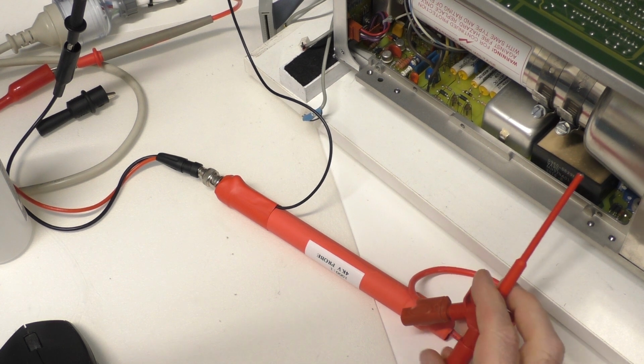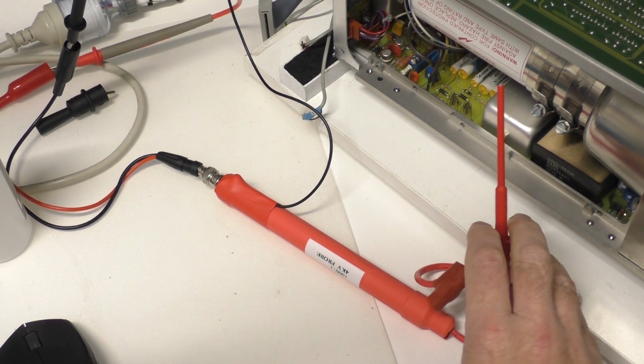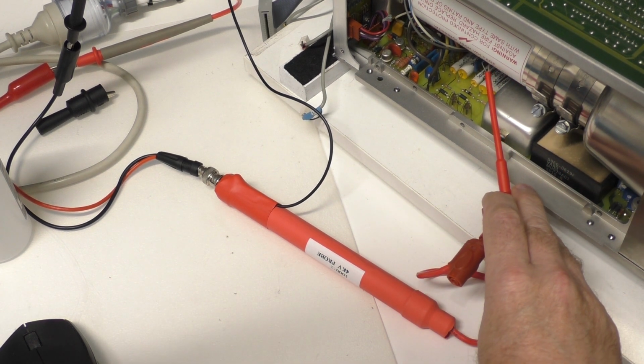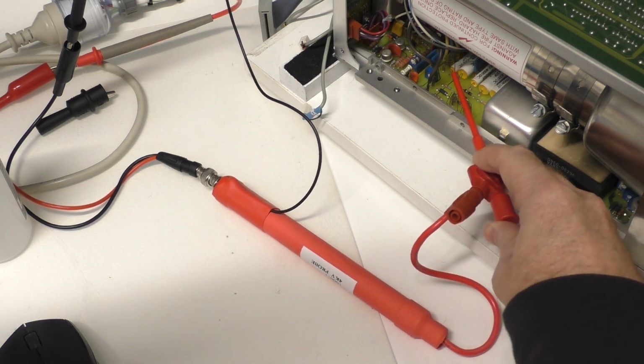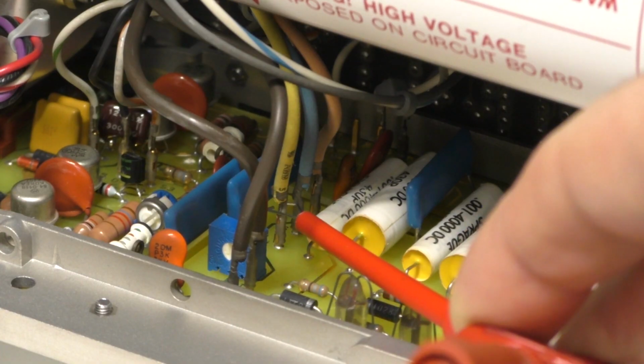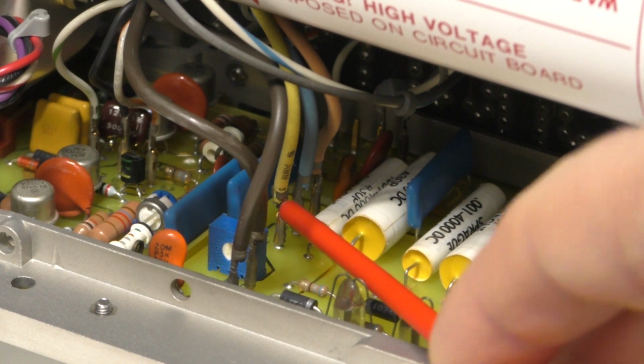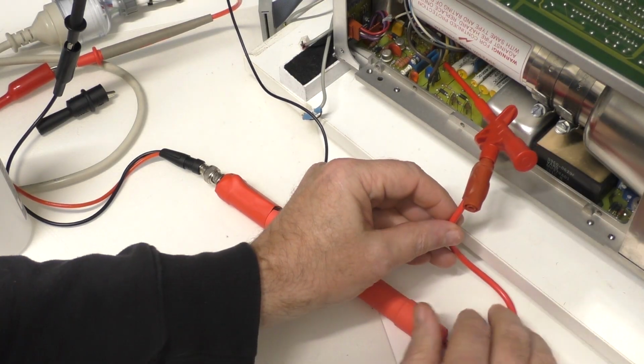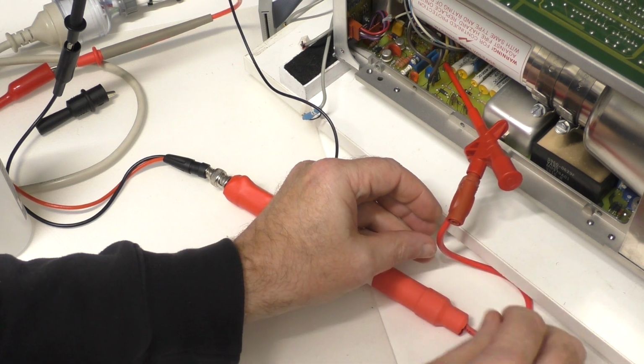Power down, and wait for supply to fully discharge. For this test we put the display on its side. Attach the high voltage divider probe to the yellow cable connector of the A4 high voltage supply board. Attach the ground of the probe to the chassis. The voltage divider outputs connect directly to the DVM.